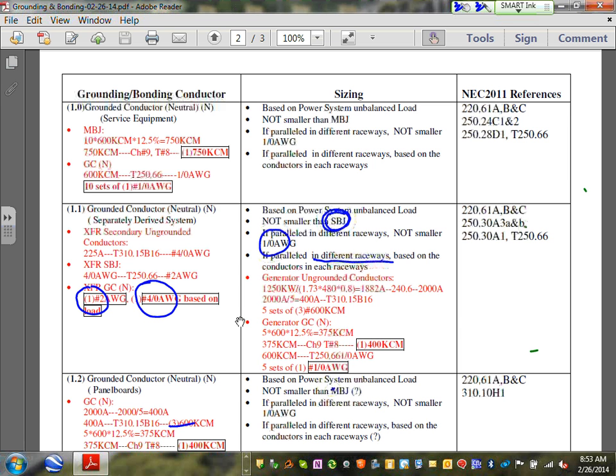So you have 2 choices. Either you go full neutral, a lot of engineers go full neutral. Okay, here's my full neutral, right here. They made the grounded conductor like we did in our project. I told you guys, if it's close to 200 amp or less, full neutral. You can pull full neutral, or you can go to the bare minimum that the code allows, which is number 2. So what's the answer, Chad?